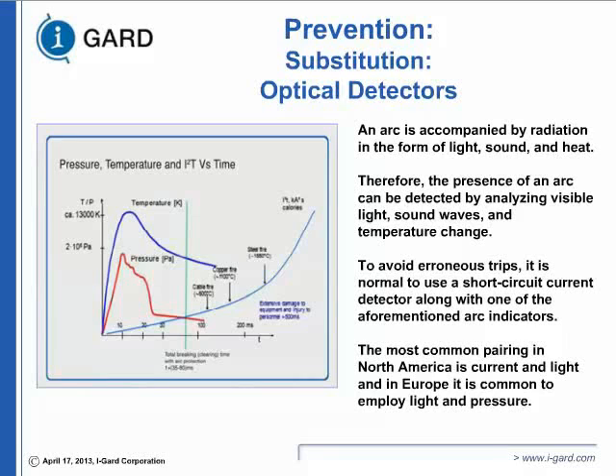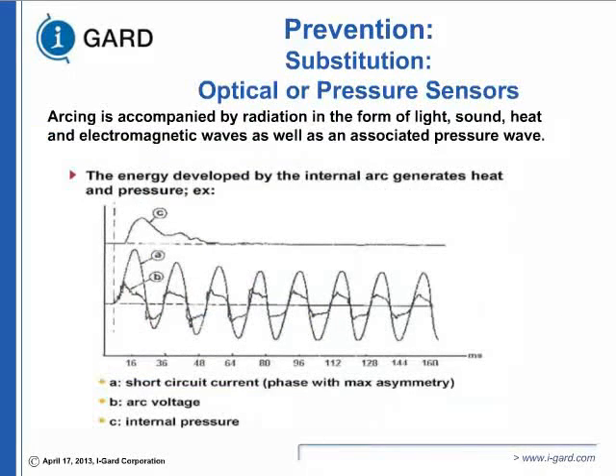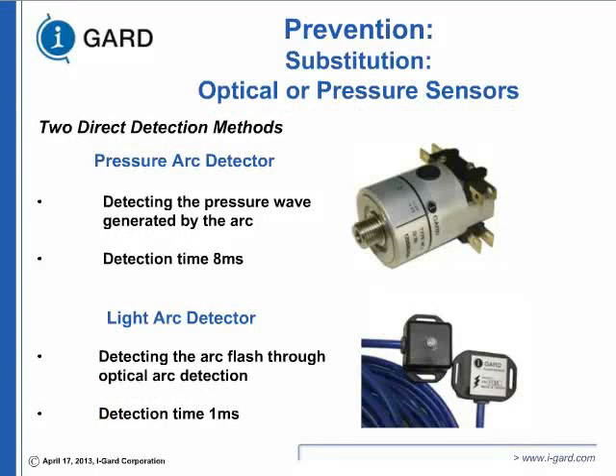So what is the difference between high resistance grounding and optical detectors? Basically, one prevents accidents, and one acts after that. And this is another picture of optical detection that shows how fast it can operate. Internal pressure will build up, so sound will pick up. Some of the technology available: pressure sensors, which is a slow process, or light arc detectors, a very fast process.